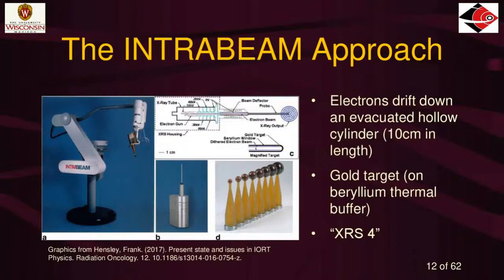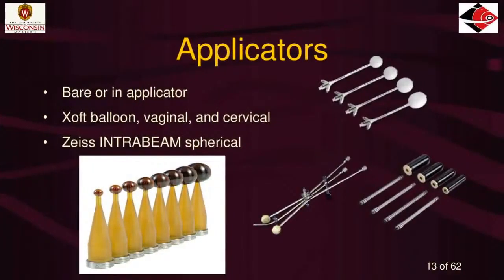Both the Xoft and IntraBeam systems have similar energy — around 50 kV. They have different applicators: the Zeiss IntraBeam spherical applicators go inside a lumpectomy cavity in the operating room. The Xoft applicators include saline balloon applicators that can be inflated and deflated, and cervical applicators made out of titanium or steel for gynecological treatments. The applicator choice affects the dosimetry, which I'll discuss in a minute.